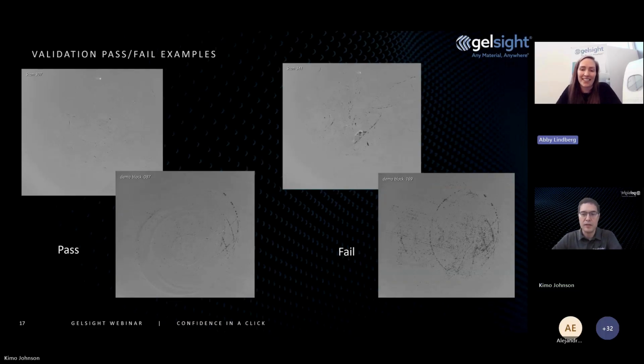Thanks. Yeah, so these ones on the right-hand side that are failing, there's a lot more light coming through. It's coming through a lot of the field of view. It's definitely affecting our measurement results. These couple that you see on the left-hand side actually end up highlighting that that top left one has a puncture mark through it. And we're kind of highlighting that there is usable space on the gel where we're measuring within tolerance. I probably still wouldn't measure exactly in that one spot where there's a puncture mark, but we're still definitely reporting within our specifications for the requirements of the validation plate.